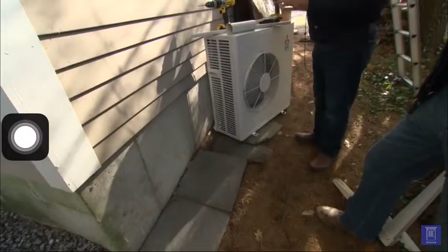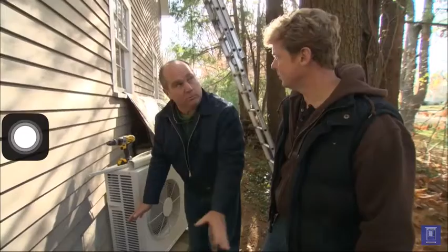We'll run that right on the outside of the building, bring it down to about here. Now at this point is where we want to put this condenser. This unit has to run in both heating and cooling mode, so if we put it down on a concrete pad like we normally do, we'd worry about snow. So we actually want to hang it off the side of the building. There are a couple of angle brackets that'll hang off of this horizontal, and I'll attach the bracket with some lag screws.